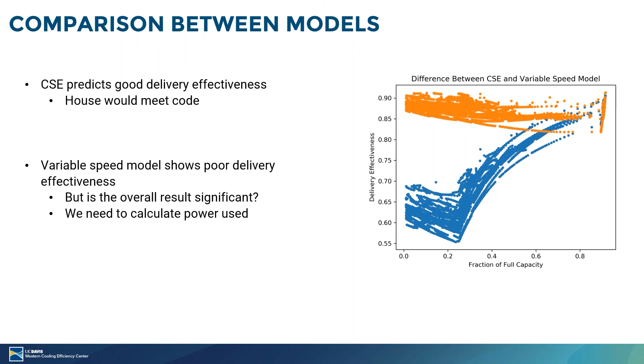Depends on how your house is constructed. The issue with builders using this software and not getting the correct answer is that they won't include roof deck insulation in the attic, for example, so the attic gets really hot in summer and really cold in winter. In that case, variable speed equipment wouldn't be better than a single speed system. But if you have both variable speed and a high performance attic, or variable speed and zoning, then variable speed is much better.